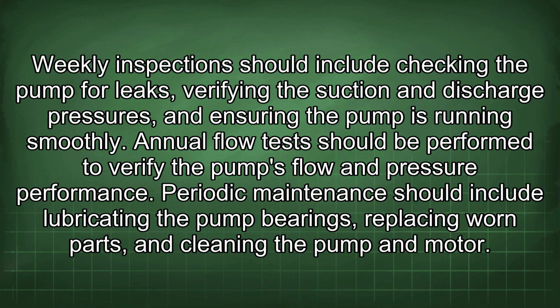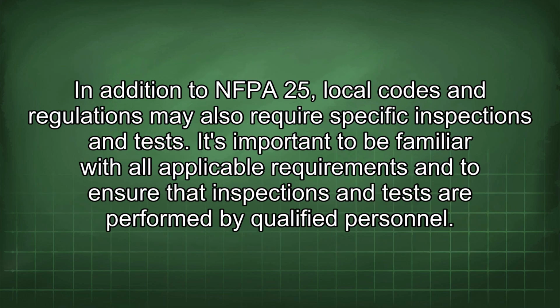Annual flow tests should be performed to verify the pump's flow and pressure performance. Periodic maintenance should include lubricating the pump bearings, replacing worn parts, and cleaning the pump and motor. In addition to NFPA 25, local codes and regulations may also require specific inspections and tests.